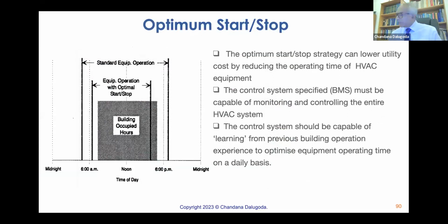Optimum start-stop strategy can lower utility costs by reducing the operating time of HVAC equipment. The control system specified, the BMS, must be capable of monitoring and controlling the entire HVAC system. The control system should be capable of learning from the previous building operation.